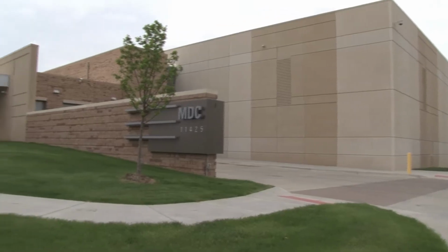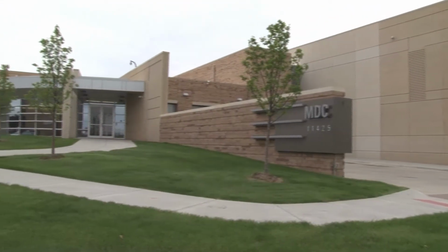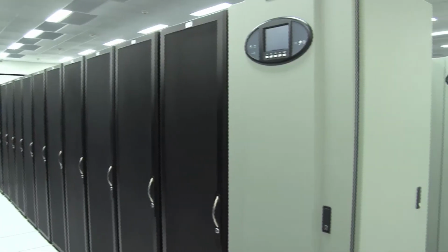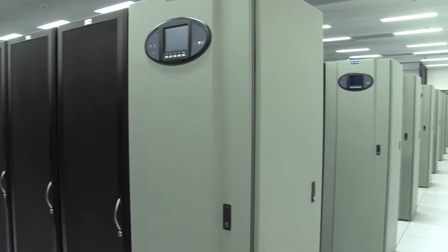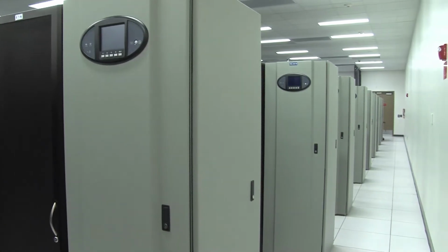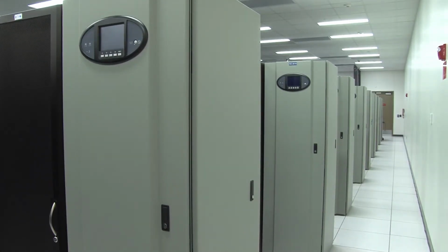CoSentry is headquartered in Omaha, Nebraska. At this time we have 6 data centers throughout the Midwest. Midland's data center was commissioned in January 2010. This is our flagship data center based on a Tier 4 design. We have 10,000 square foot of data center floor. The power density is 150 watts a square foot.